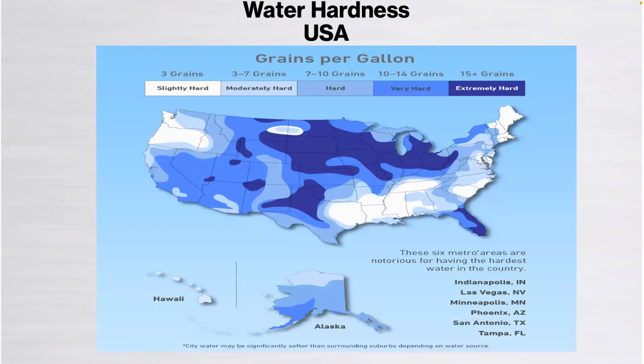And to give you an idea of hard water in the United States, depending on where your projects are, as you can see, certainly the Illinois area is extremely hard. So if you have leaks, especially on a heating system, and you don't know you've got the leaks because you're not measuring the water loss on your RPZ valve, you're losing, let's say, glycol inhibitor, and you're introducing hardness.